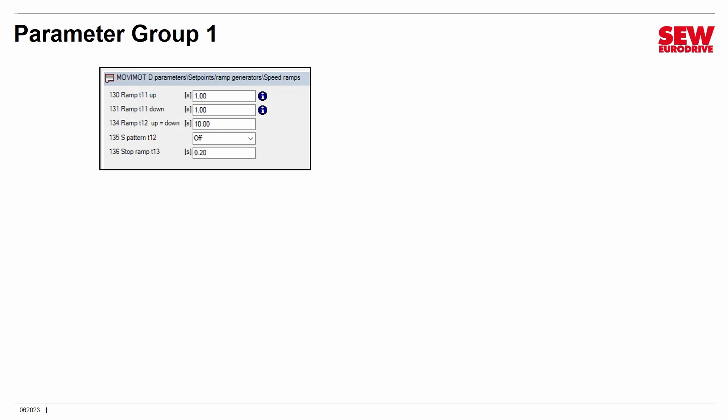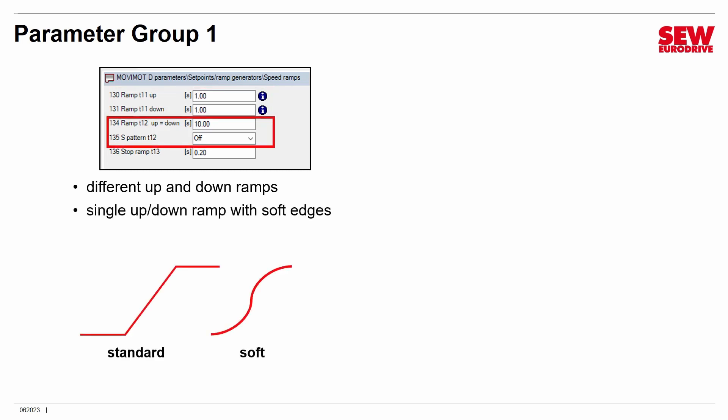Let's start with Parameter Group 1, which includes ramps. This gives you a lot more flexibility in how you speed up and slow down. Instead of just a single ramp from the T1 dial, you now have different up and down ramps — note the 'I' symbols next to these two parameters, meaning you must have the T1 dial disabled to change them. You calculate values using the same equation from earlier sessions. You also have a single up-down ramp with programmable soft edges — S-ramps — where acceleration and deceleration are more gradual and gentle.